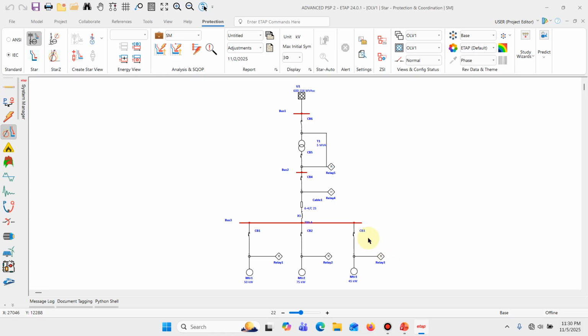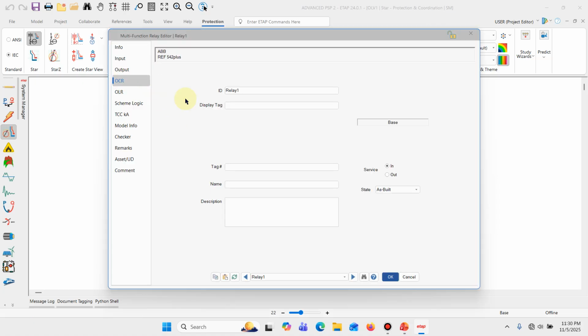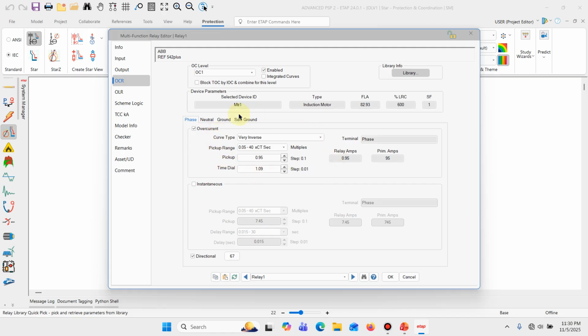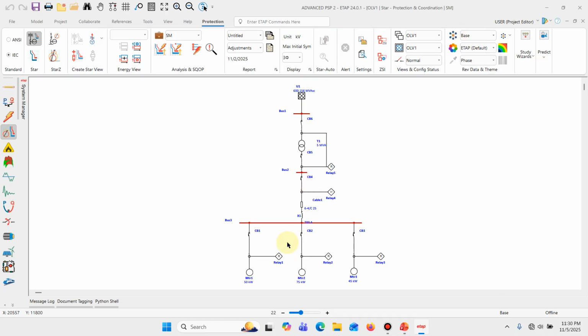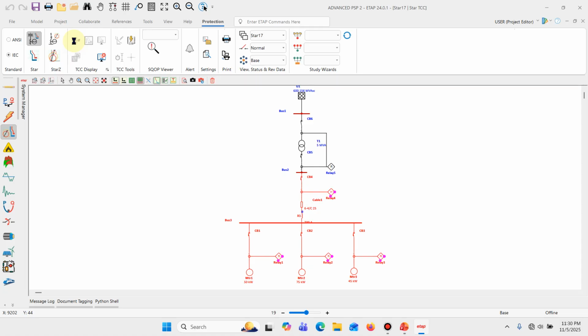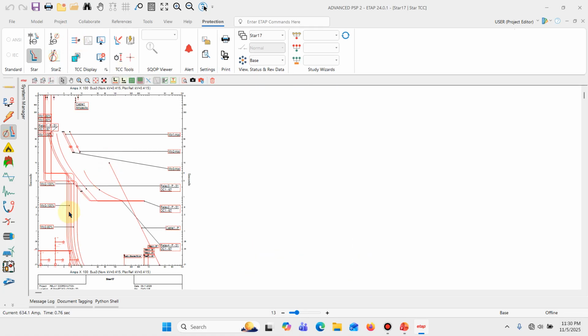So these are basic overcurrent protection schemes, and we can test and simulate to see how the system operates when there is a fault. So just for instance, we can view the relay settings. This is the settings for this particular relay, and each of the other relays have similar settings. So we can take this entire section, and we come over here where we have create star view. Let's see what our protection coordination really looks like. Okay, so we can zoom in on our one line diagram and we can bring it out over here.